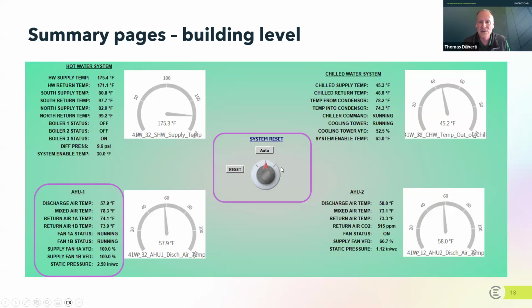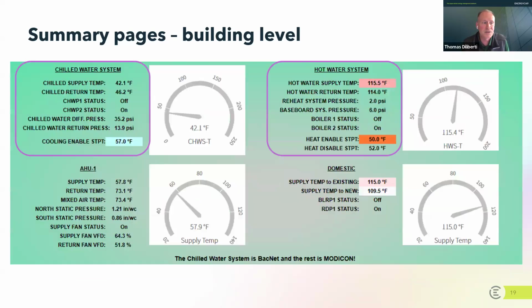It would be essentially a scheduling button, but it would be the same type of master control that would allow you to put all buildings in a school district, or all the appropriate ones, into a setback mode. So you're not heating buildings that have a snow day. So that's what I wanted to point out here again: don't disregard a master button. If there's a way that your organization can use some type of master control, think about it, program it in, talk to the people in order to execute that.